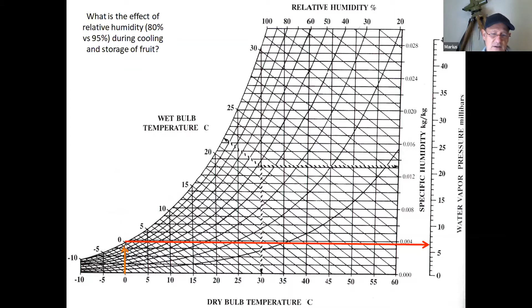However, if we're looking at it from a storage perspective, the system changes. Now the fruit is at 0 degrees Celsius, 100% humidity because it's already cold. And at the 80% relative humidity, we can see the fruit is running at 6.5. And with a poor cold room running at 80% humidity, we see that the vapor pressure in the air is 5 millibars, giving me a 1.5 millibar deficit. The good cold room running at 95% humidity has a vapor pressure of 6 millibars. The fruit is also going to be 6.5. So in other words, the vapor pressure deficit in the good cold room is only 0.5 millibar.